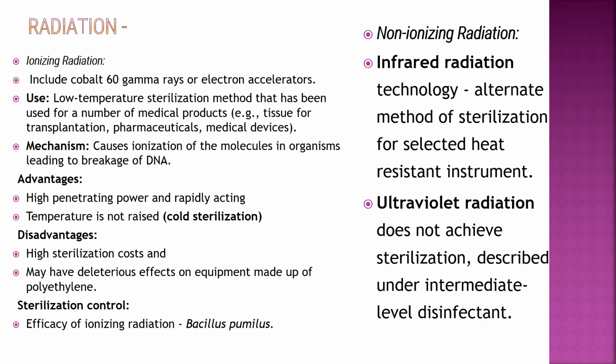Advantage: high penetrating power and rapidly acting. Temperature is not raised, so it is also called cold sterilization. Disadvantage: high sterilization cost and may have deleterious effect on equipment made up of polyethylene. Sterilization control: efficacy of ionizing radiation is checked by Bacillus pumilus.